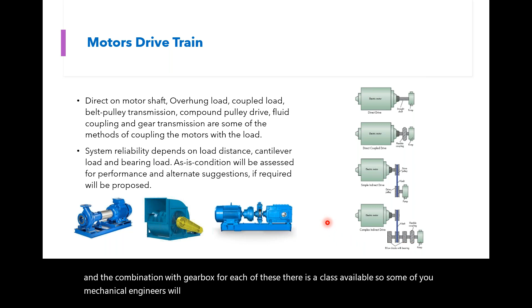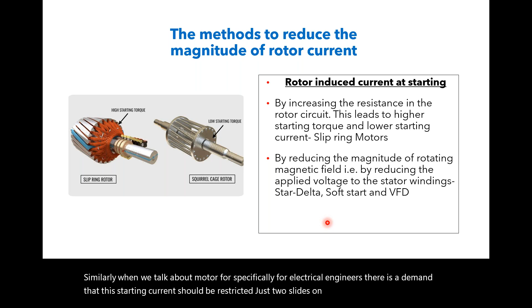Similarly, when we talk about the motor, specifically for electrical engineers, there is a demand that the starting current should be restricted. Just 2 slides on this. The restriction of starting current is very critical, because an unrestricted starting of a motor would draw between 6 to 8 times its rated current from the grid. And all this demand will be placed on the transformer. So you cannot go on oversizing the transformer and the cable for a difficult starting current.